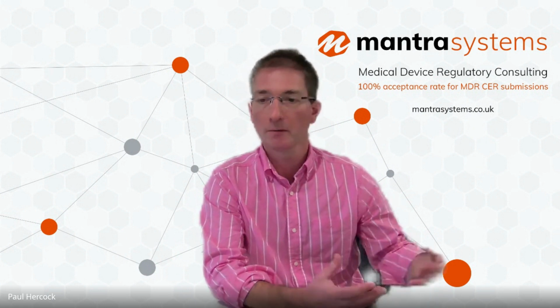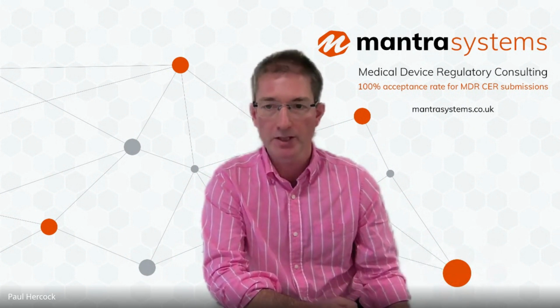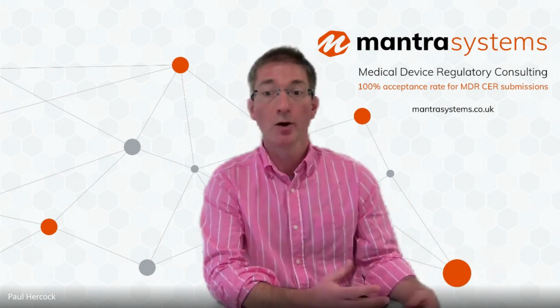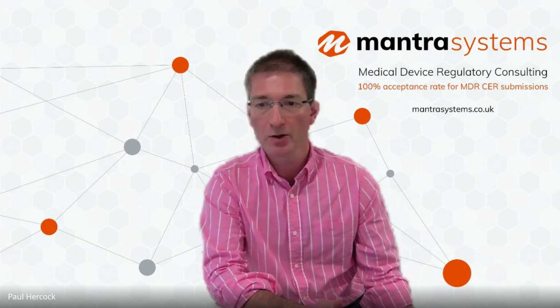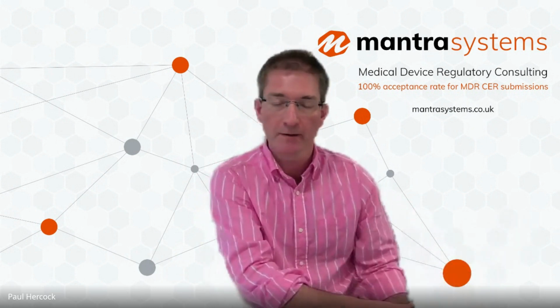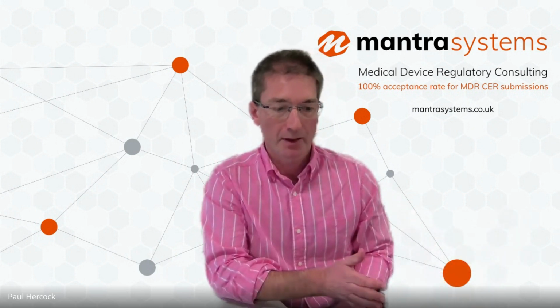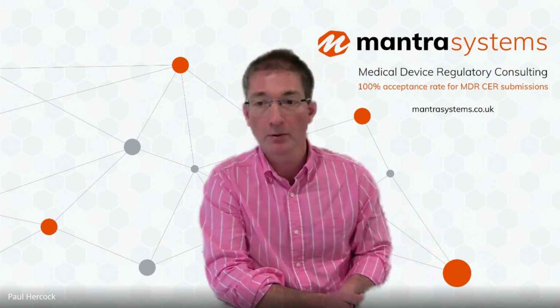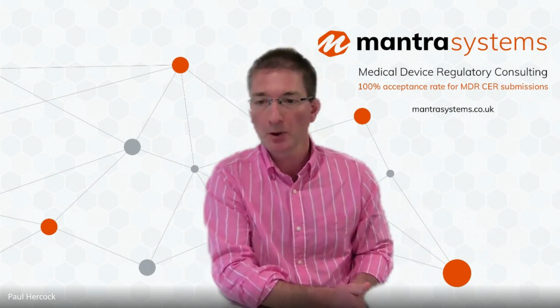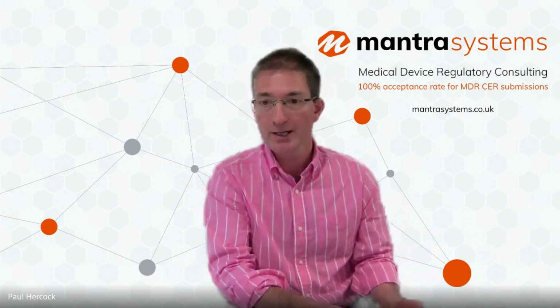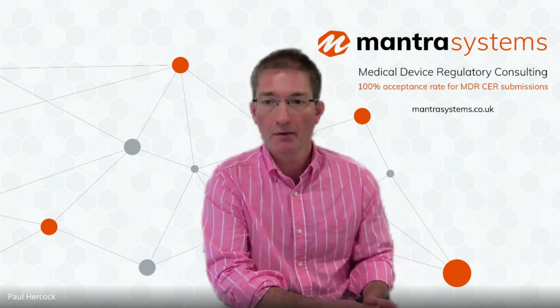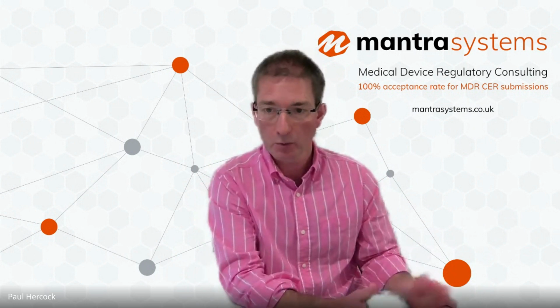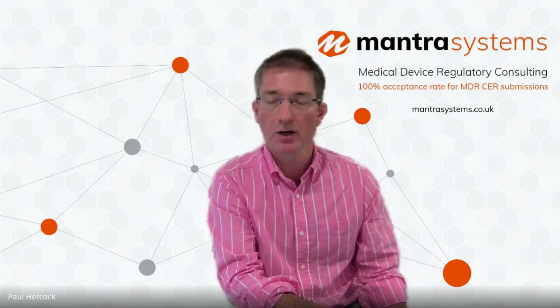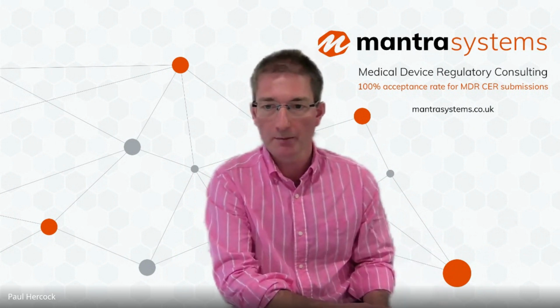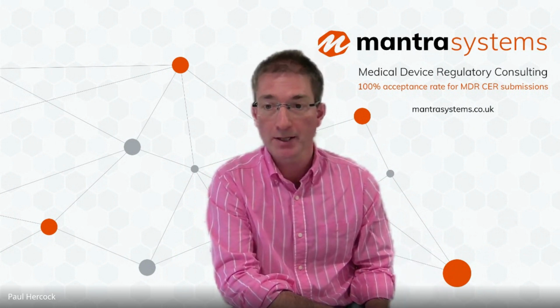So you might say, well, my device is completely novel, there's nothing else like it out there, there's no point doing a state-of-the-art review because it always relates to something completely different. The fact of the matter is, the state-of-the-art review, if done properly, will tell you what people are currently recording when addressing this clinical problem. And that's your start point for what clinical parameters you need to focus on and what would be the most appropriate for a performance criterion.